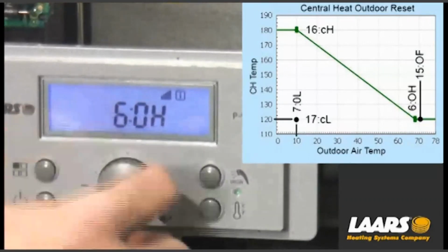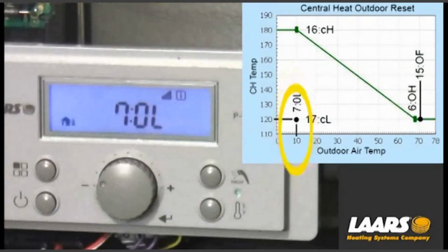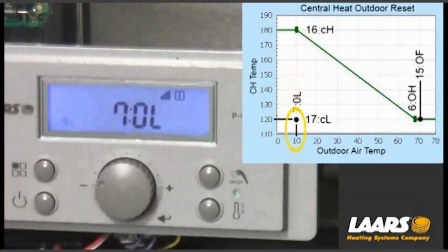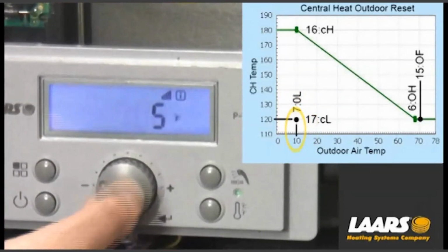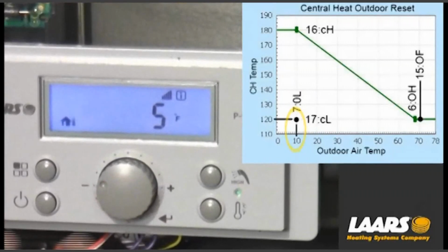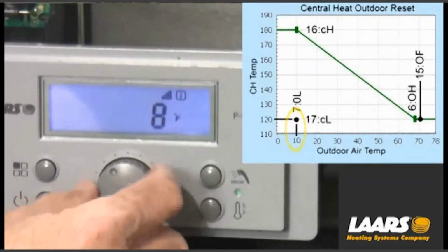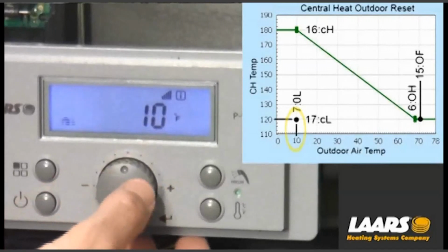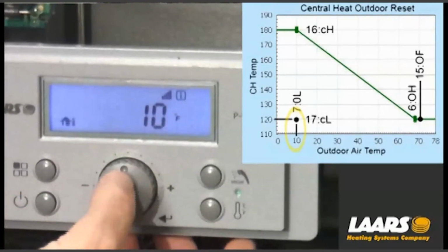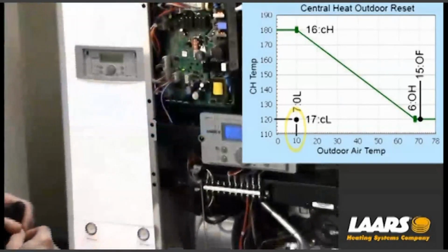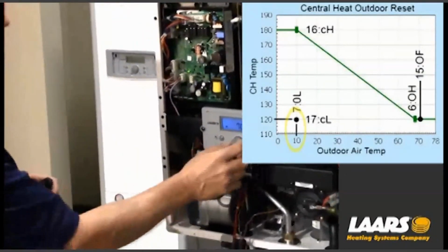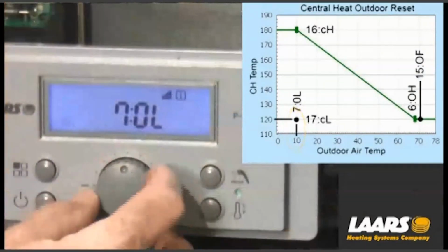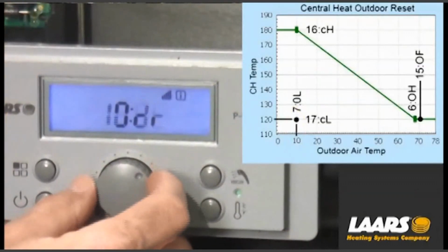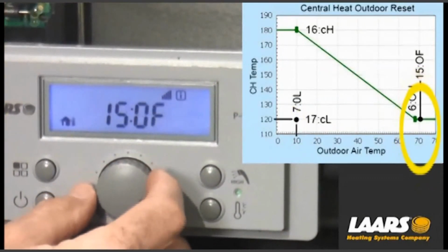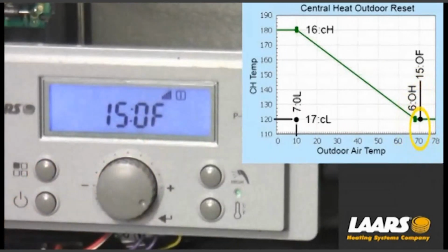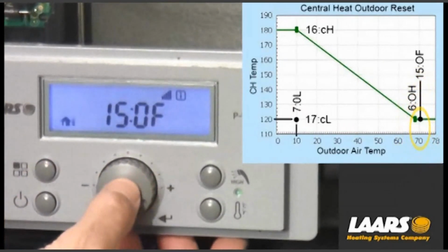Now that I'm back to the screen where it says 6OH, turn it once. 7OL, that stands for the outdoor air temperature low. So I press select, and in this case, I'm going to adjust that to 10 degrees of outdoor air. Now that I'm at 10 degrees, I'm going to press the select button again, and we'll store that. Now what I want to do is scroll to 15 OF, and that is the off point. That is our warm weather shutdown.